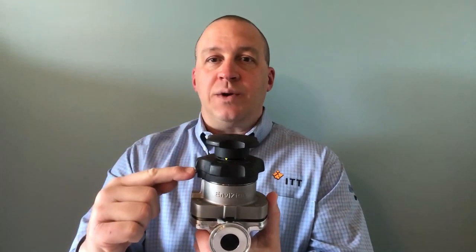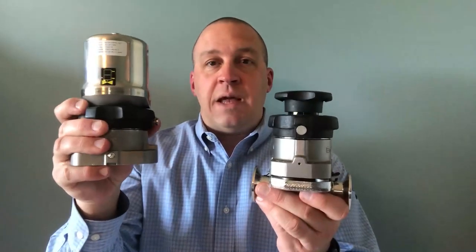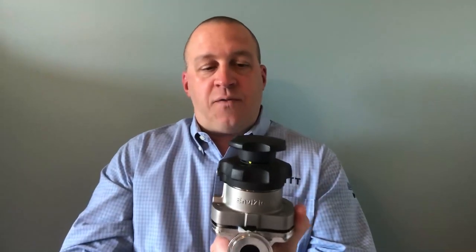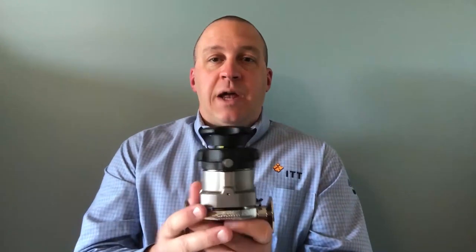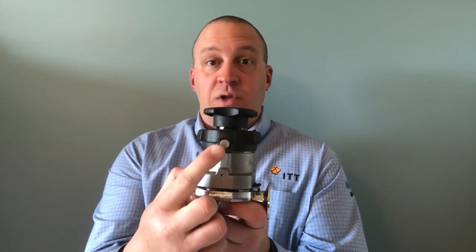From a nomenclature standpoint, a couple things before I begin. The manual version of the EnviZion valve — the first thing you probably notice is there's two handwheels. The top handwheel is the normal operation in-service open-close handwheel, used as the valve is being used in-service. The lower handwheel I'm going to call the cover handwheel. That's the handwheel used in the diaphragm changeout process primarily — it's what's going to open and close the valve and take it apart and put it back together. To begin your diaphragm changeout process, the first thing you want to look for is the locking pin on the cover handwheel.